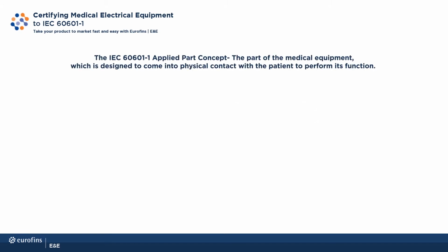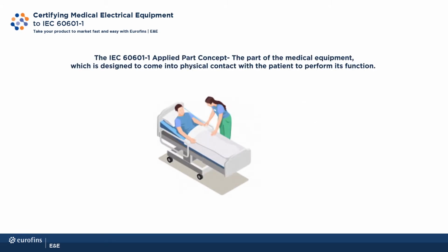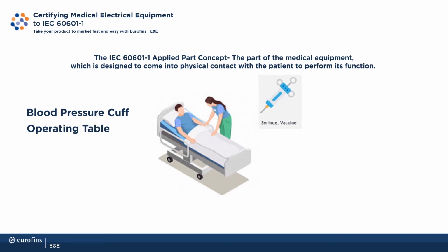As a result, the medical standard IEC 60601-1 has a concept called the applied part. This refers to the part of medical electrical equipment that touches the human body. Examples of this are a blood pressure cuff, an operating table, the sensor of a multi-parameter monitor, or the leads of a defibrillator. If the equipment is used around the heart, it needs to have the most isolation from electricity possible. This is the type CF applied part.